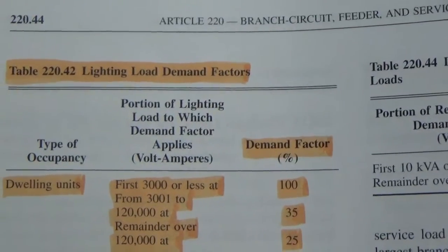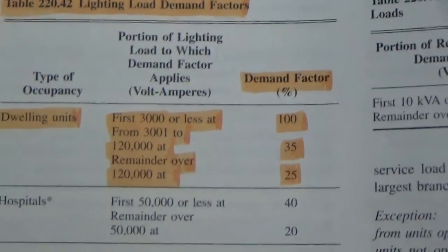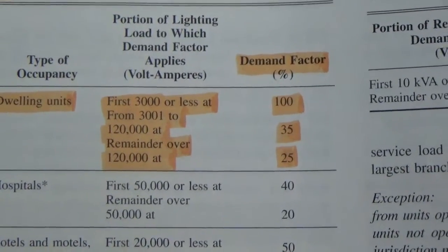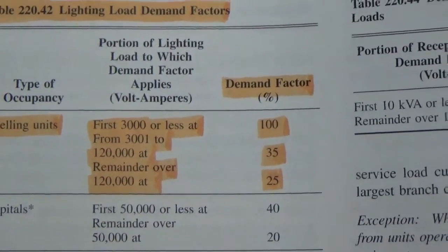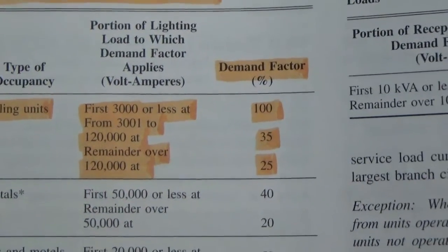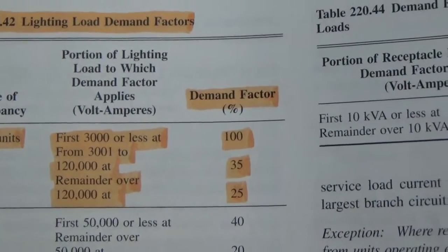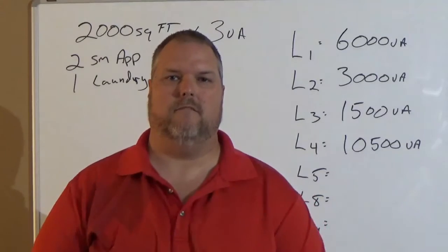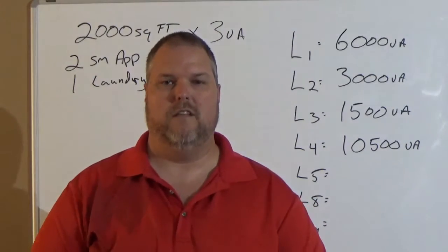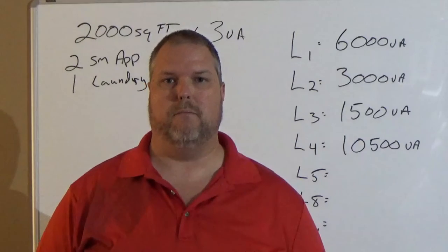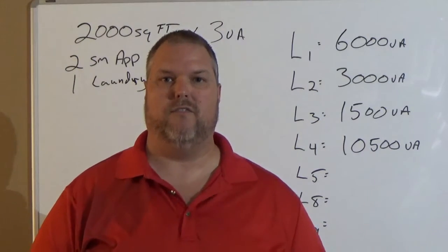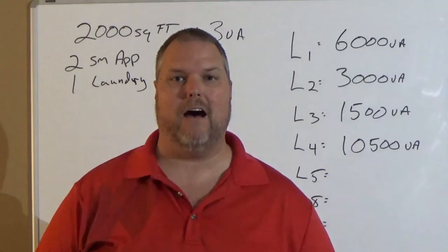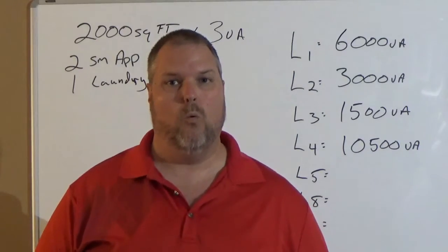We have to go back and look at the code. Table 220.42, lighting demand loads. We're looking at dwelling units. First 3,000 or less, we take it 100%. 3,001 to 120,000, we take it 35%. The remainder after the 120,000, we take it 25%. The first thing we have to do is minus 3,000 from our total number. Because, according to 220.42, we have to take the first 3,000 and take it at 100%.